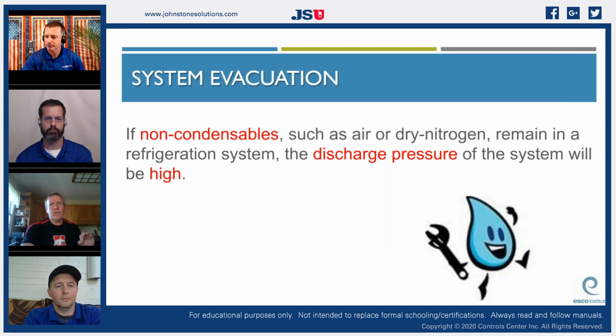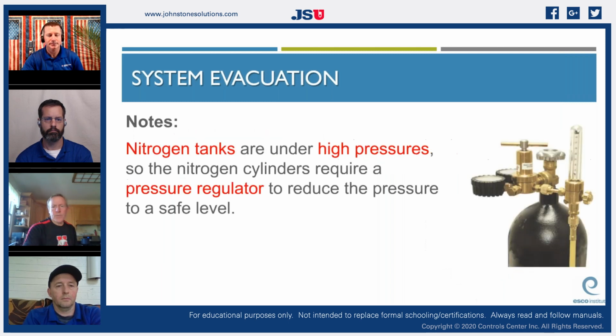In fact, I actually had a situation where we at least determined there was, what do they use to leak check in the factory? Helium? I forget what it was, but there was actually dirty air inside the system and the head pressure was going crazy. So we actually had to remove the refrigerant, evacuate it, put virgin refrigerant back in it, which was the only way we got the head pressure down. So we determined that there was some non-condensable inside of it. Right. And I believe, working with a man on that one, that they think it just got left. I think it was helium they used in the factory to check for leaks.